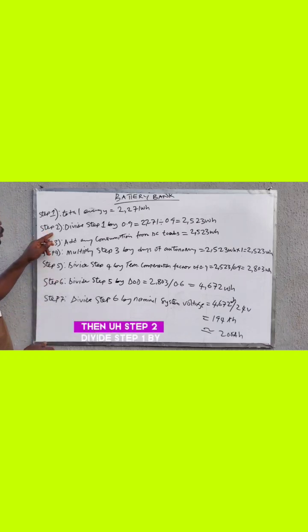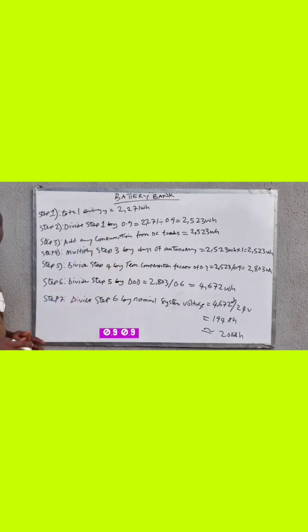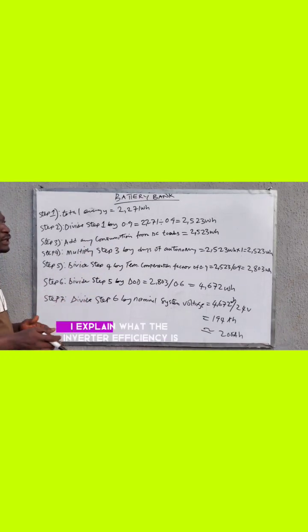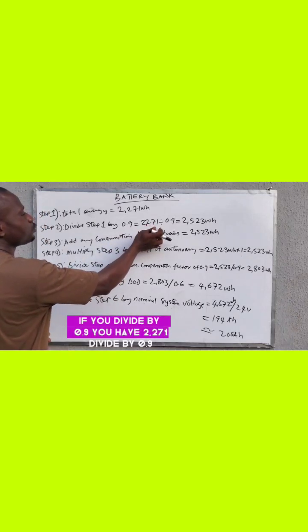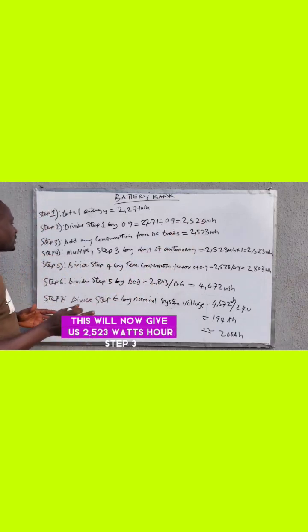Then step two: divide step one by 0.9. 0.9 here is the inverter efficiency. Check my previous videos - I explain what the inverter efficiency is. So if you divide by 0.9, you have 2271 divided by 0.9, which gives us 2523 watt-hours.